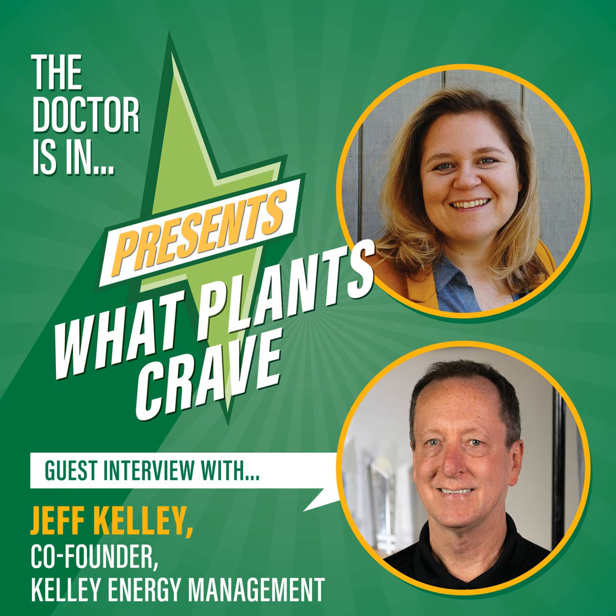Do you manipulate the results after you get them from 3D Plus, or are you confident in the results that they're putting out with the inputs that you're putting in? We're confident as long as it corresponds to the real world. So if we run an energy model and it says the flower room is 400 degrees F, well, we made a mistake there somehow.